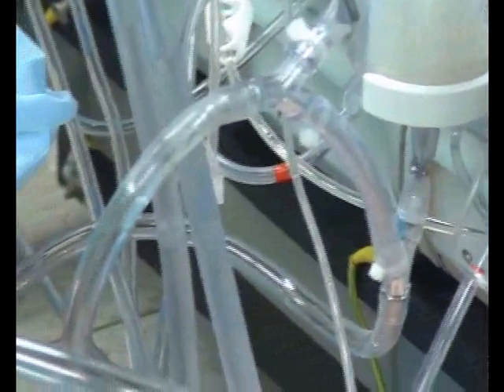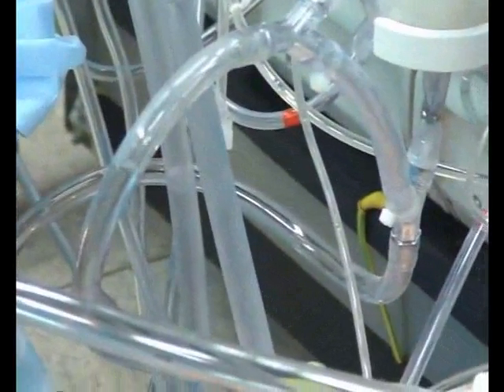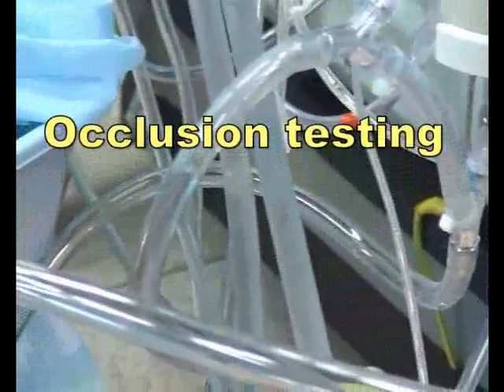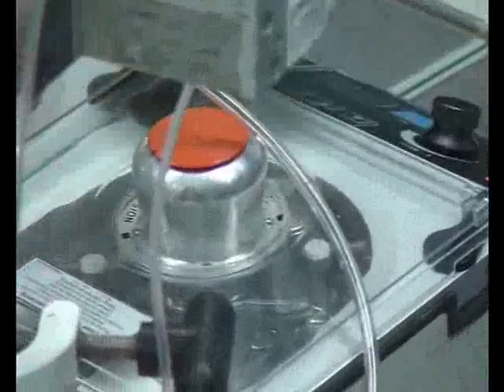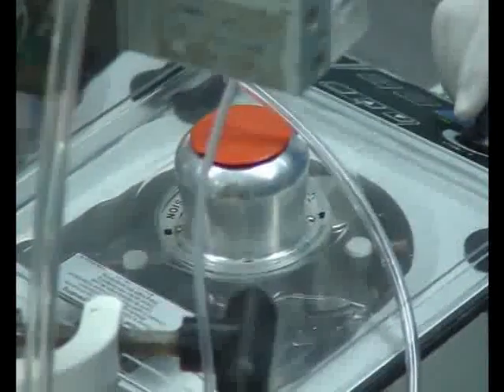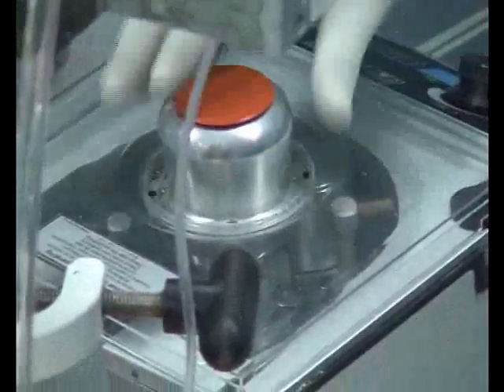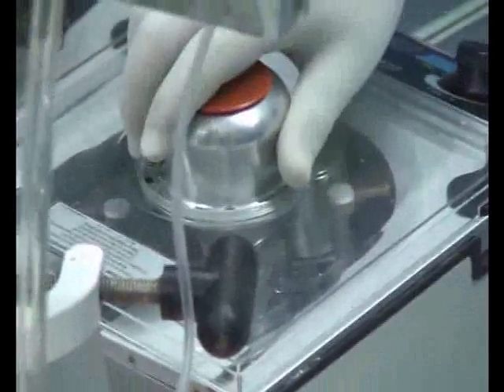The occlusion test is performed on the arterial pump. The pump head is adjusted for no more than 1 inch fall in height per minute. The arterial filter is deaired. The cardioplegia line is deaired. The priming fluid is vigorously circulated.